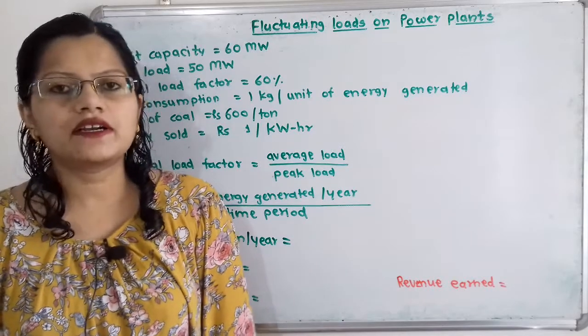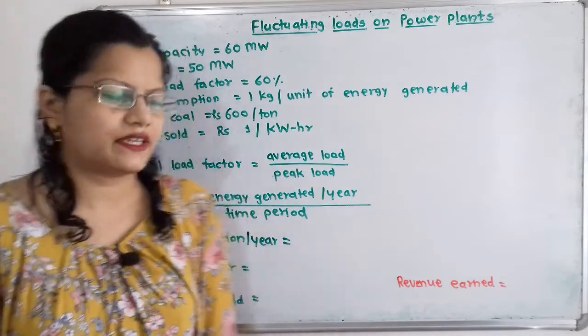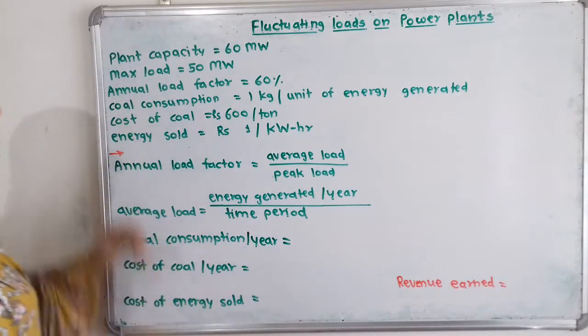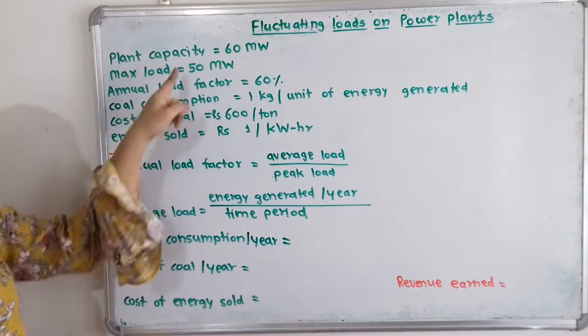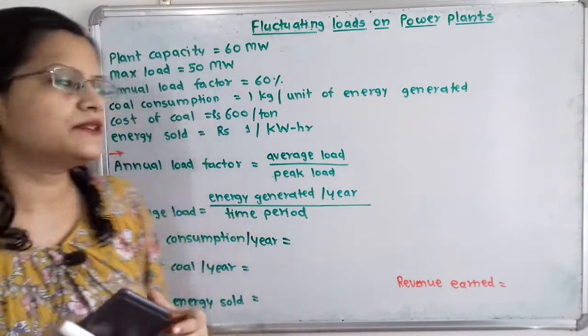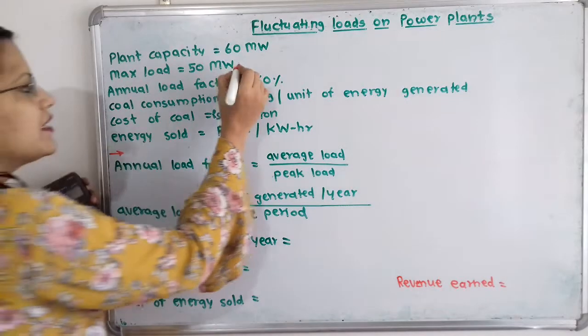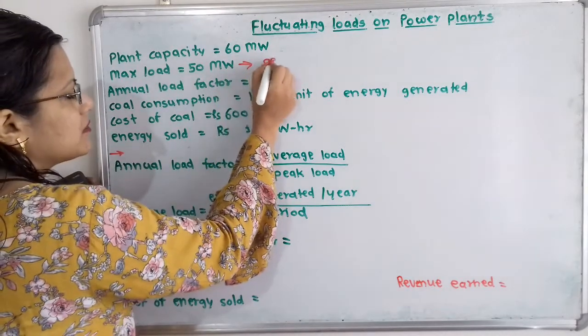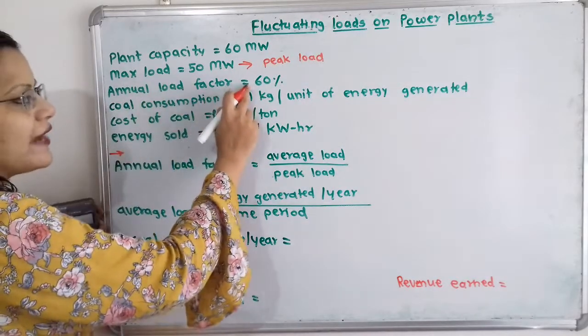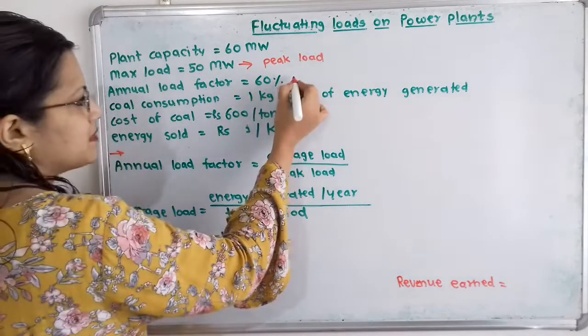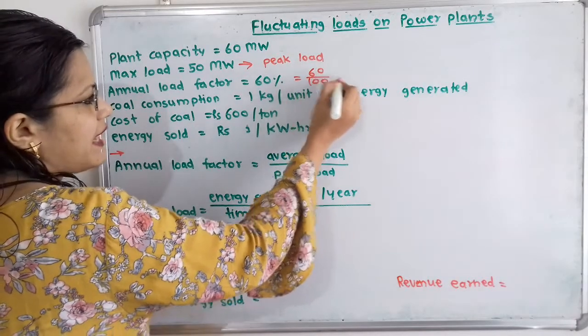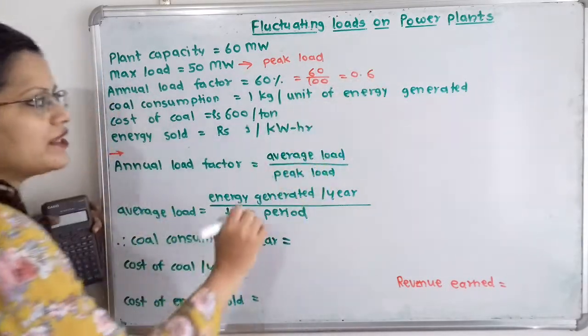Let us first understand what is the given data. Plant capacity is 60 megawatt. Then maximum load, that is 50 megawatt — this maximum load is also known as peak load. Then annual load factor is 60%, which we write as 60 divided by 100, equal to 0.6.